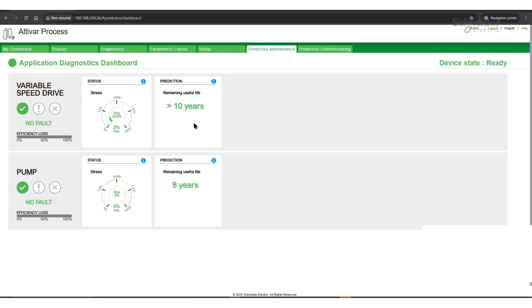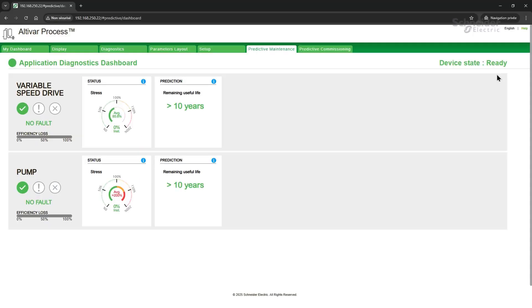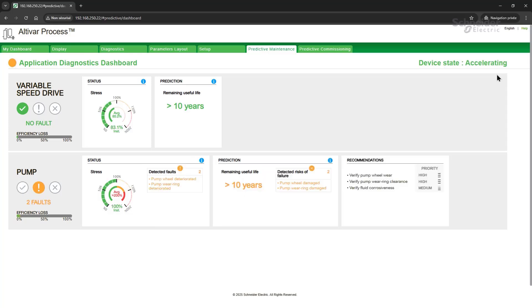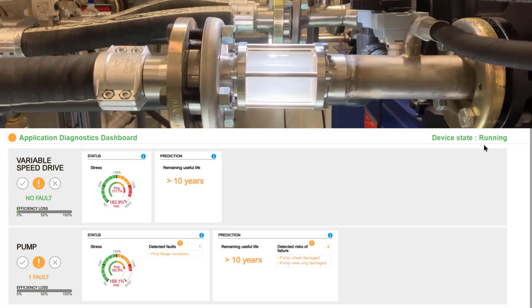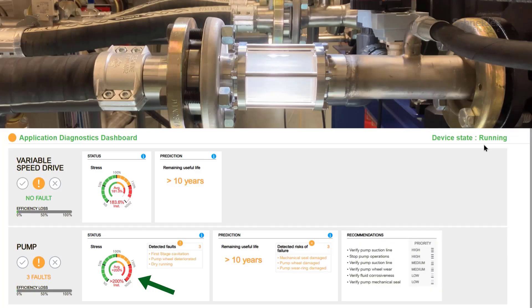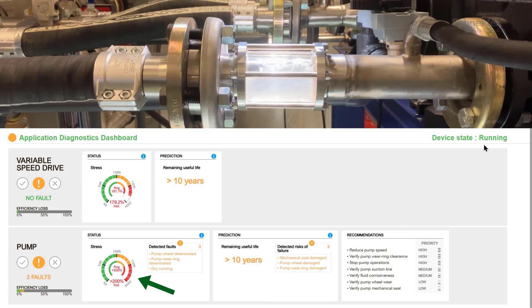Now we can see the predictive maintenance application diagnostics dashboard with information about the variable speed drive and the pump. Running ATV PREDICT, we can monitor various KPIs for performance analysis. Devices ready — let's start the application. During acceleration, the dashboard updates in real-time based on current conditions. This phase is more demanding than stable application, so messages may appear and then disappear until we reach steady state. We will gradually start to close the inlet valve, allowing us to observe the development of cavitation within the system. As we proceed, the dashboard begins to display a noticeable rise in stress levels accompanied by new messages related to prediction and recommendation. These updates provide valuable insights as we analyze the situation further.